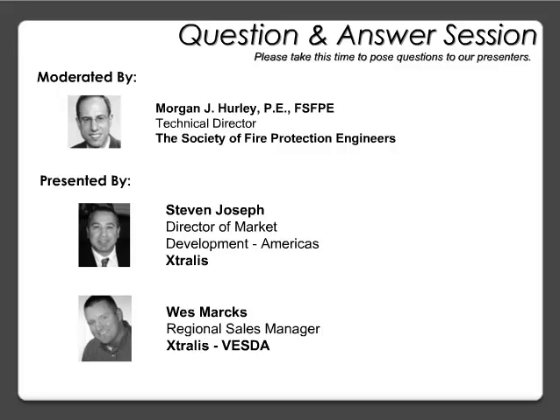Thank you for that. This is hopefully a pretty easy one. Someone had asked about piping materials that one would use with the aspirating smoke detection system. Sure. So the pipe that's typically used is a 3/4 inch Schedule 40. It's a CPVC, so it's a fire-rated, plenum-rated tubing. And that typically would come pre-labeled or pre-identified as air sampling tubing.